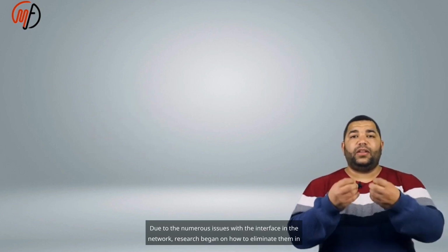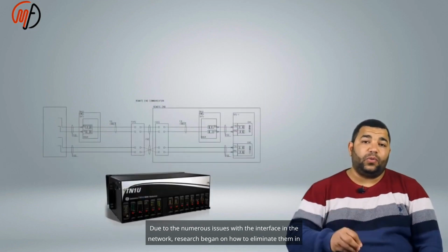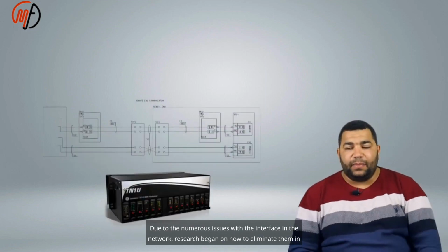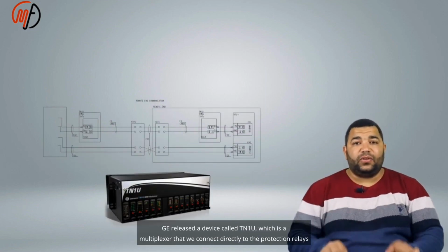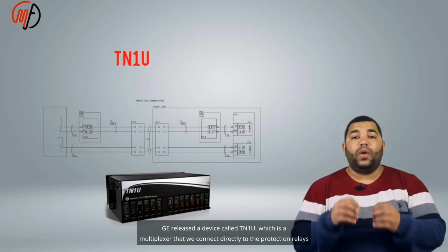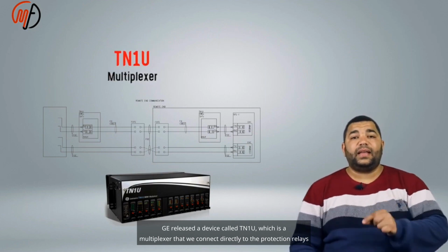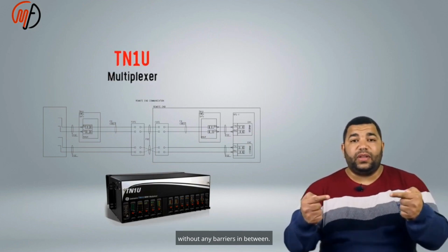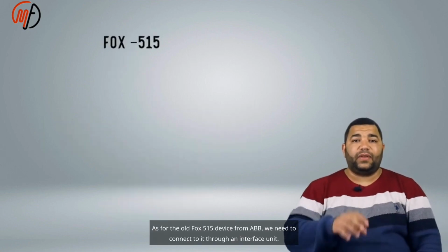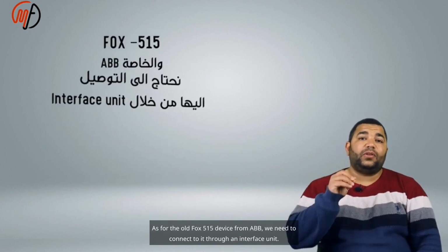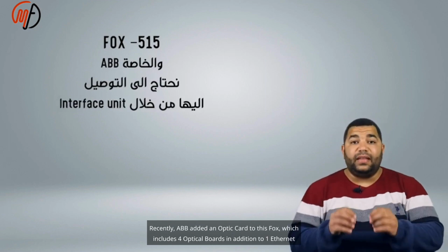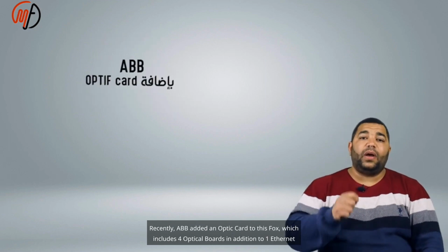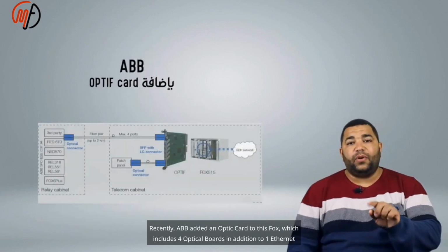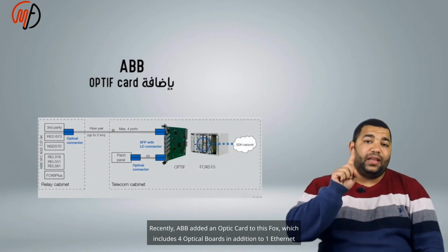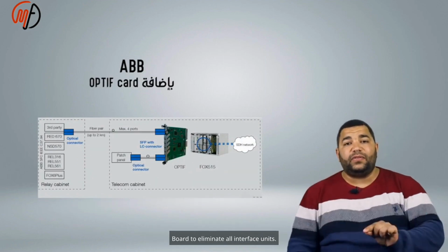Due to the numerous issues with the interface in the network, research began on how to eliminate them in modern stations. GE released a device called TN1U, which is a multiplexer that we connect directly to the protection relays without any barriers in between. As for the old Fox 515 device from ABB, we need to connect to it through an interface unit. Recently, ABB added an OPTIF card to this Fox, which includes 4 optical boards, in addition to 1 Ethernet board to eliminate all interface units.